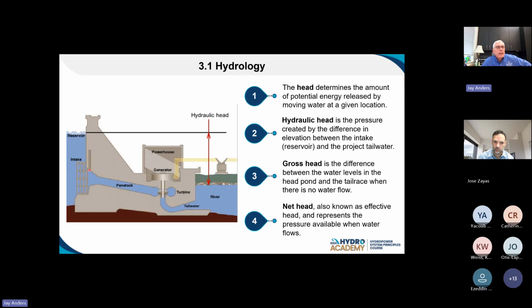A lot of times this intake structure, the size of it, the shape of it, what it looks like, any obstructions, like trash racks in the way, that obstructs my flow. All of those things take a little bit of energy out of the water, or create a loss for the water if it could just flow freely right into my turbine. So that goes back to what Jose was talking about earlier: when the design engineer starts doing his design, there are economic considerations — what should the penstock look like, how big of a trash rack should I have, how fast should I let that water flow? So those are some examples.